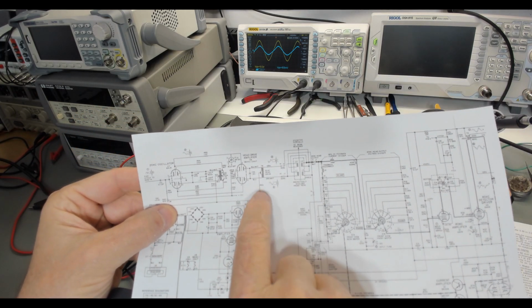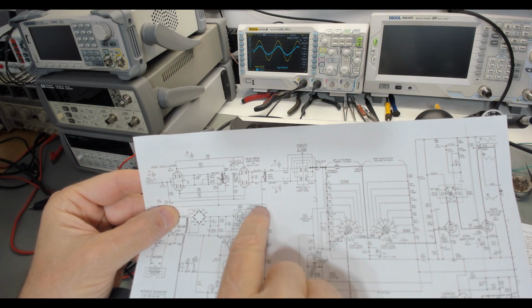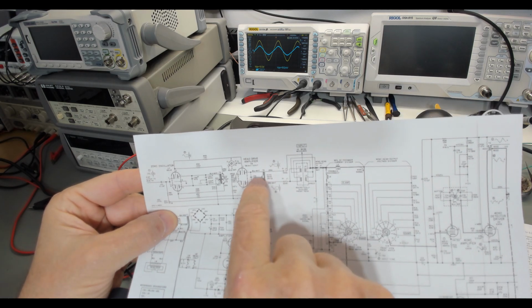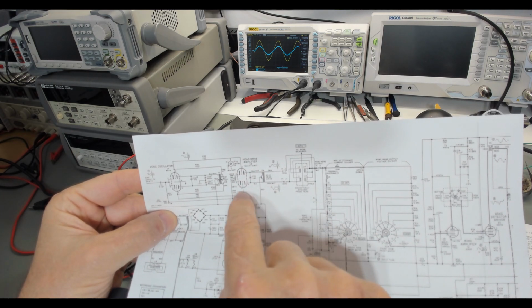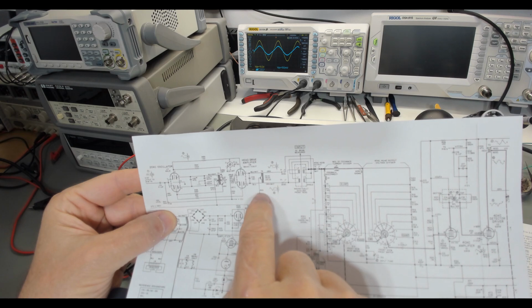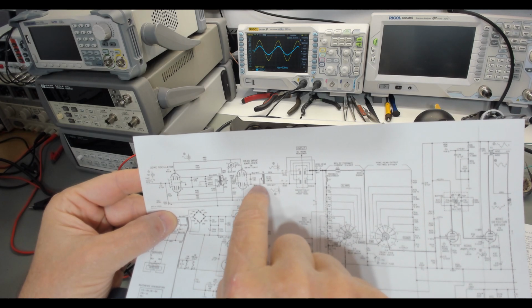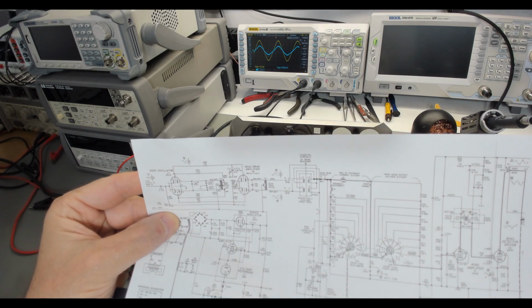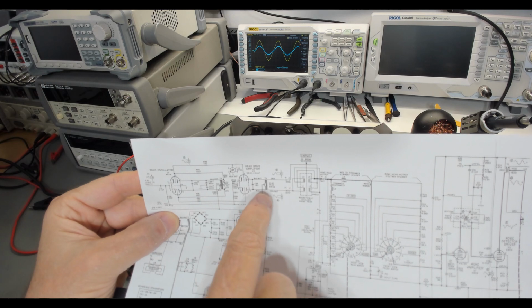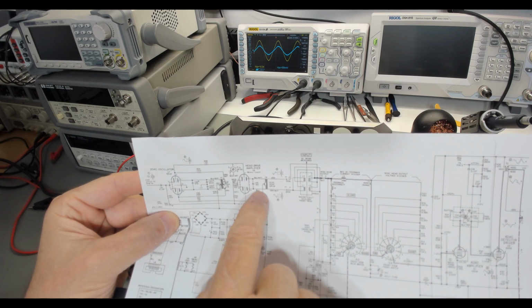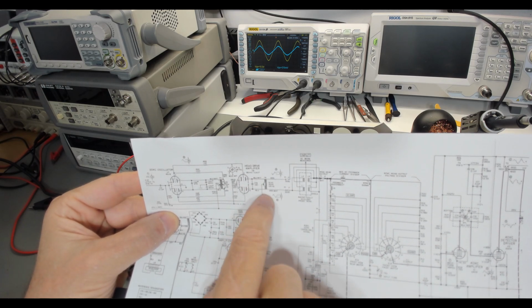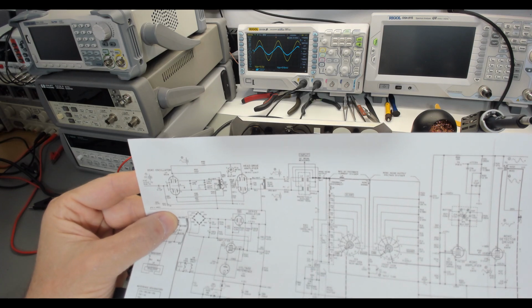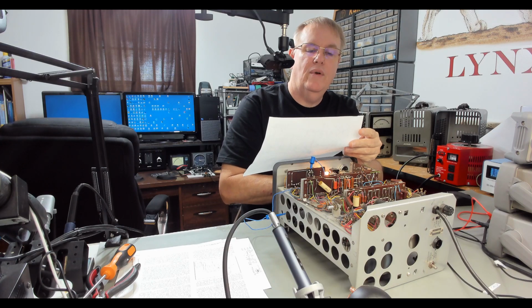If you look here, you've got one of the wires comes off. That's where the currents for each side are going to. Okay. There's really no reason why these would be dramatically different. So I'm going to go ahead and remove the blue and blue-white from the tube, the red from the circuit board. I'm going to pull that transformer out.